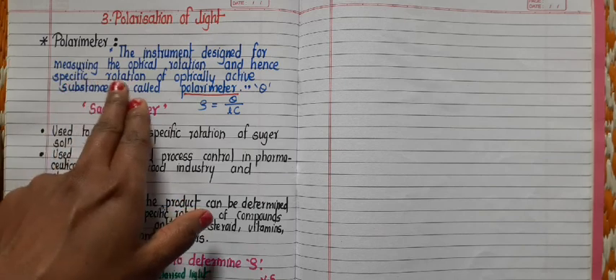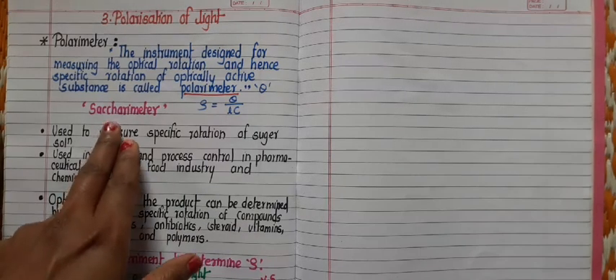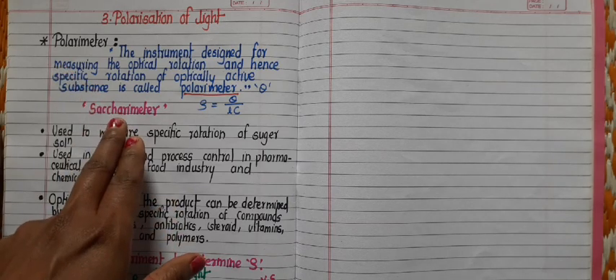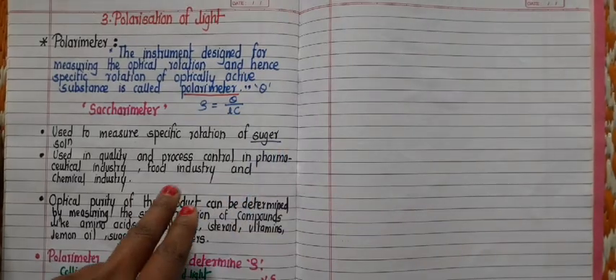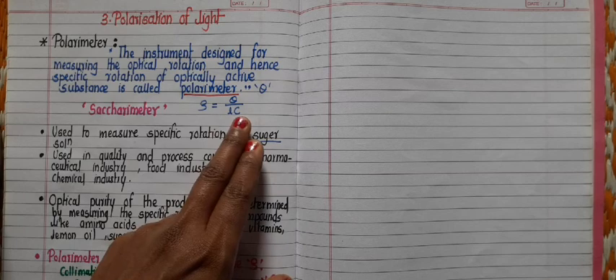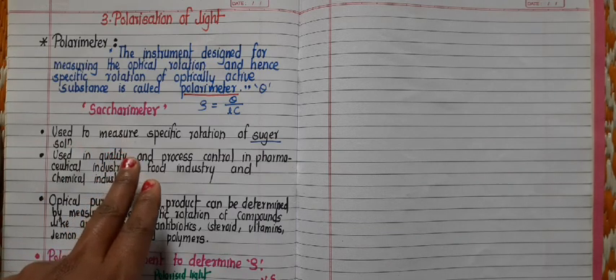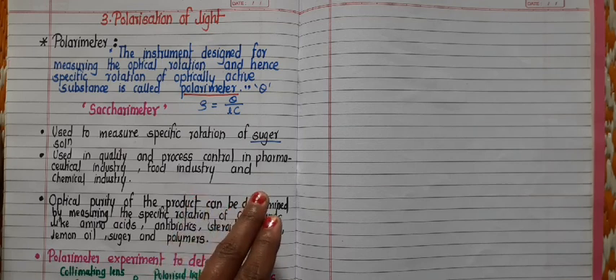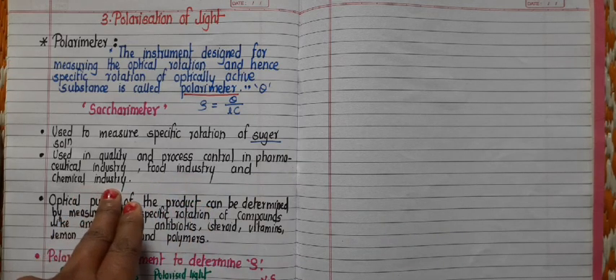By using this polarimeter, we can measure specific rotation for any optically active substance. Another name for this polarimeter is saccharimeter, because it is specially used to measure specific rotation of sugar solution. We can also calculate the concentration of sugar using a polarimeter. That is why this polarimeter is used in the sugar industry, pharmaceutical industry, and food industry.